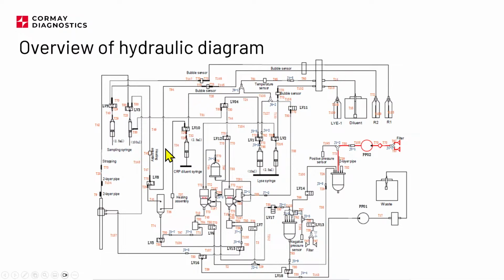And we are splitting into two circuits. This is the CRP diluent syringe. Right now we will not talk about this part, but let's go to the hematology part. Another Y, and we also have this valve here. It's supplying diluent to this part of the circuit, and this is used for aperture rinsing. And we have this part of the circuit, three-way valve, diluent syringe, and then we are splitting between the heater for WBC analysis and the RBC chamber.